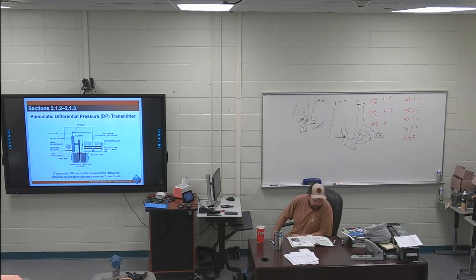Page 10, I've got those 3 bullet points in the bottom left, along with the little 2 sentences below it. Notice that the spans of all 3 models have minimum span limits that are higher than the true 0 point. A minimum span limit above the 0 minimum range is referred to as an elevated 0.